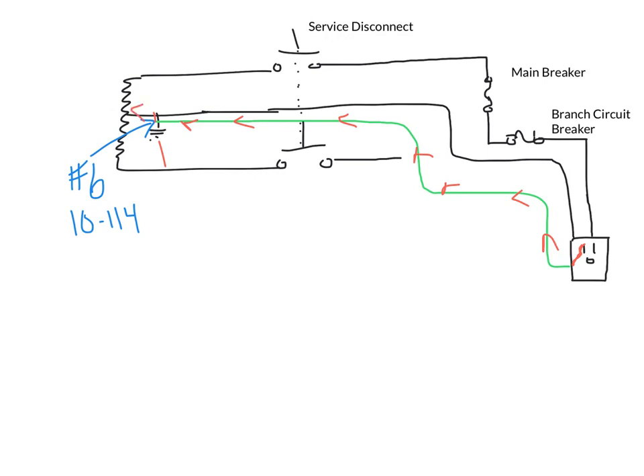It completes a circuit back through the transformer, through those nice big shiny copper conductors, and the idea is that once it completes that circuit, one of our circuit breakers, one of our overcurrent protective devices, is going to open up. Now, the code doesn't really care which one, as long as something opens up under a fault condition. But the real intent of bonding here is taking fault current back to the source. That's why not only our bonding conductors have to be sized large enough to carry that fault current, but it's critical in your installations to make sure that your bond path is low impedance, it's low resistance. You make sure you tighten down all those screws.